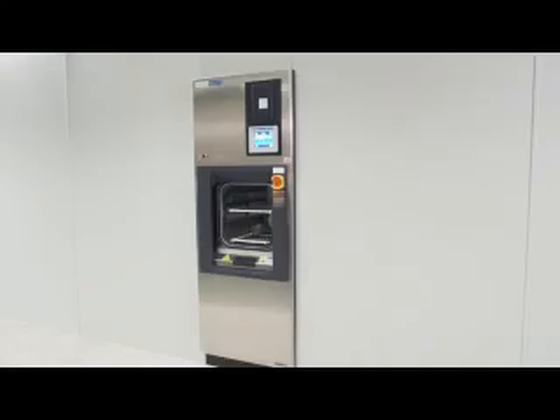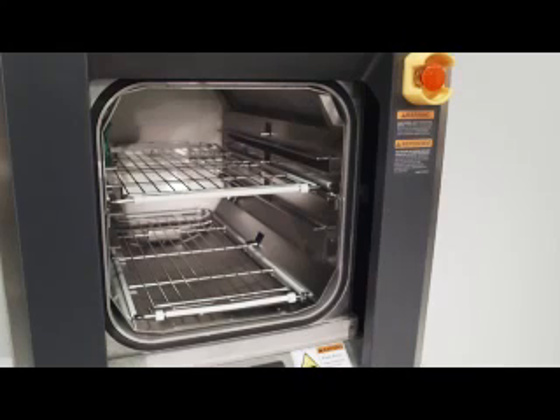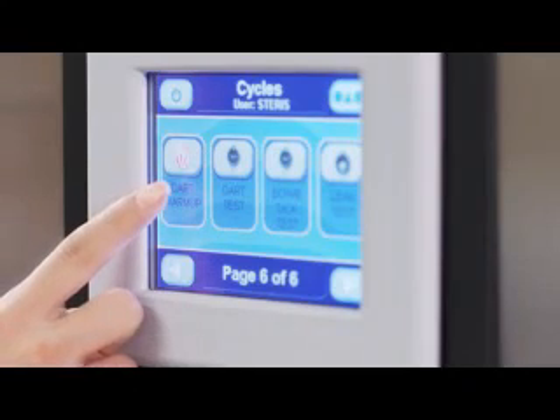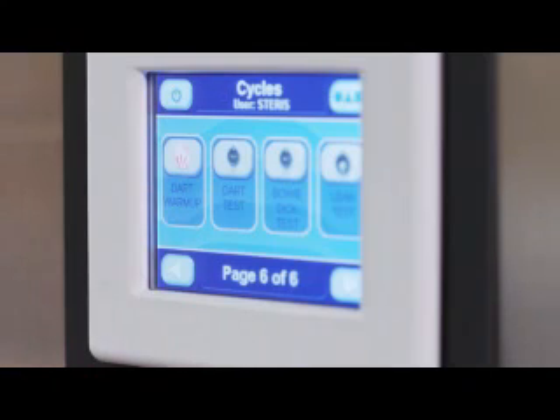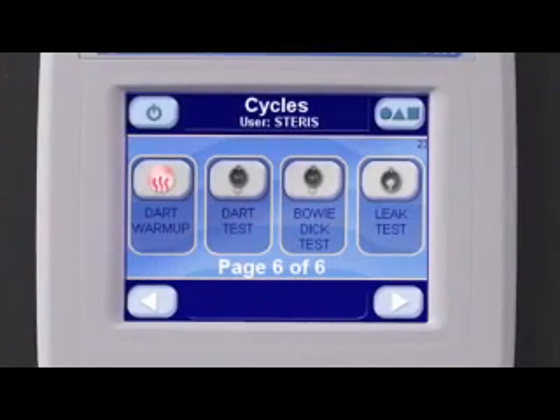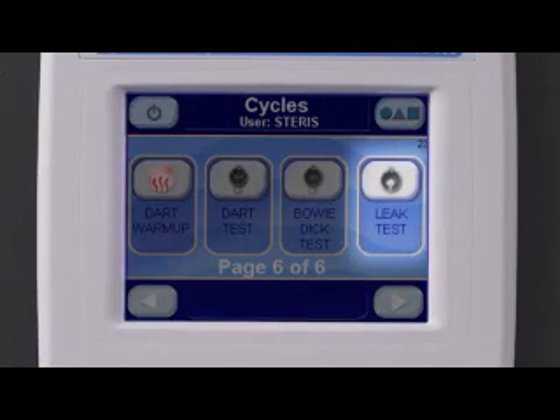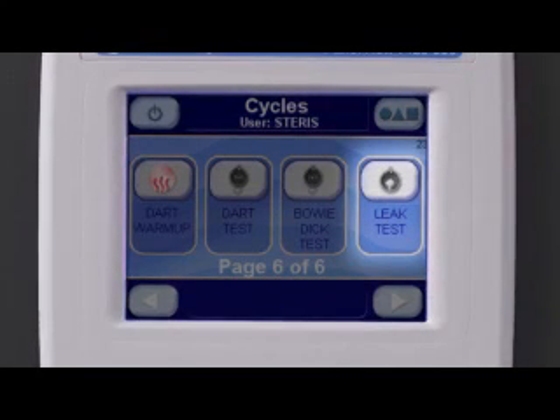A vacuum leak test should be run once a week to ensure there are no leaks in the piping or door seal. To ensure valid test results, always run a warm-up cycle before performing this test. After the warm-up cycle has completed, you can initiate the leak test by pressing the leak test button. The entire vacuum leak test cycle is also documented on the printout and includes a leak rate value.